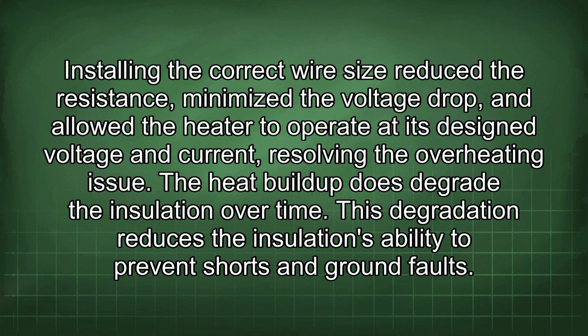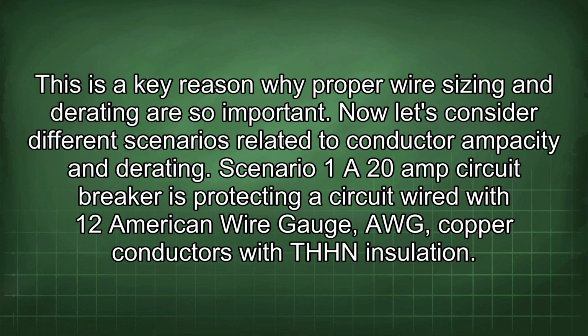The heat buildup does degrade the insulation over time. This degradation reduces the insulation's ability to prevent shorts and ground faults. This is a key reason why proper wire sizing and derating are so important.